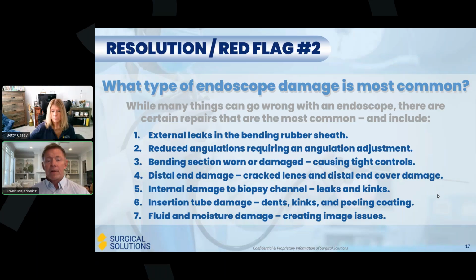Distal end damage, very preventable type of damage. And whenever you see the word cracked or dented or chipped, that just means it was, I don't want to say mishandled in a bad way, but it was either dropped or something impacted that particular part of the scope. The distal tip of the flexible endoscope has glass lenses down there. It has a plastic cap at the end. If it accidentally slips out of your hand and hits the countertop or the floor, those items will chip and crack. So it's certainly an area of the scope that you want to pay attention to. And again, whenever you're handling a scope, another awareness point is to exercise caution.